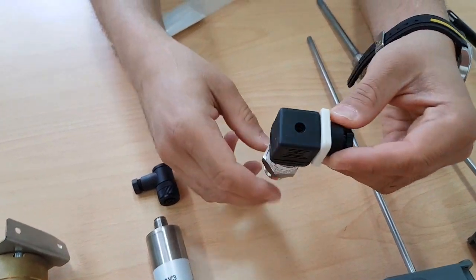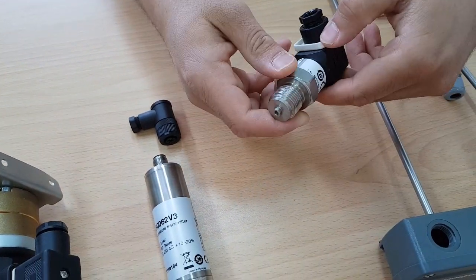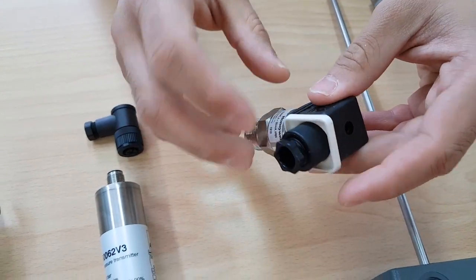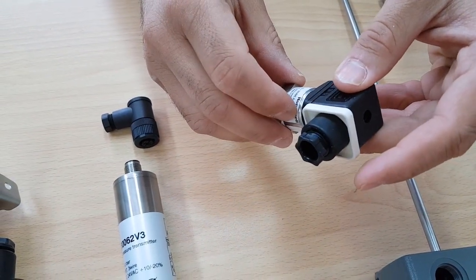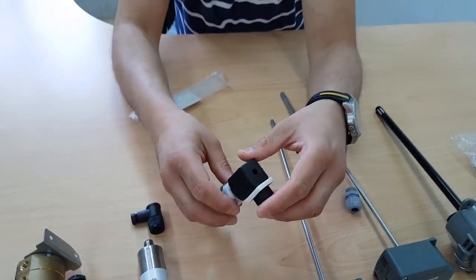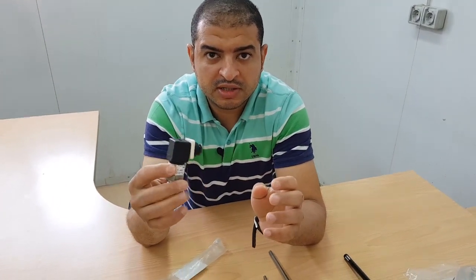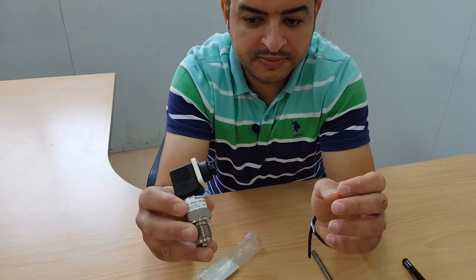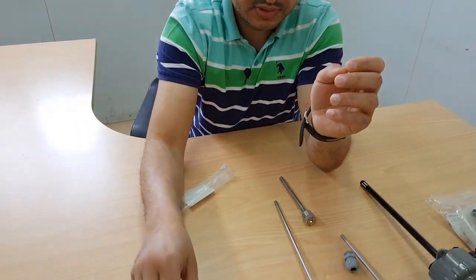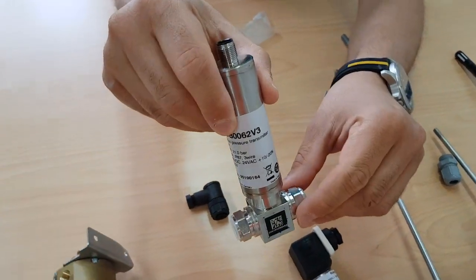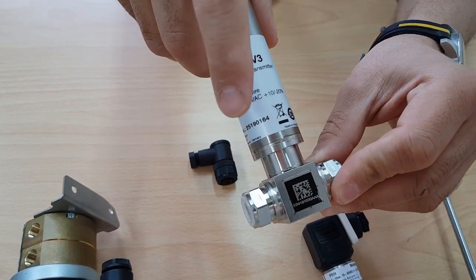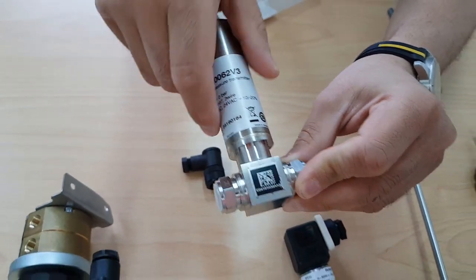Here, this is a pressure sensor, used to check the pressure on the line for a chilled water system. For example, if I need to know the pressure out from the chilled water pumps, I will use it on the supply line of the chilled water pipe. This is a differential pressure sensor or transmitter. This measures the difference of pressure between the supply and return line of the chilled water system.